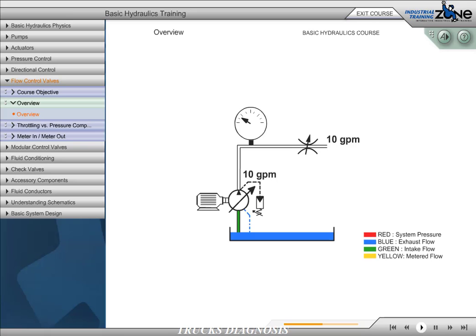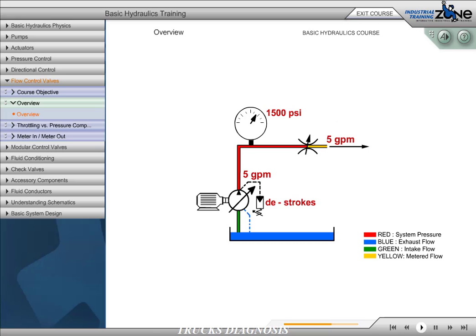When flow control is used in a pressure-compensated pump, fluid is not pushed over the relief valve. As pressure approaches the compensator setting of 1500 PSI, the pump will begin to de-stroke, reducing output flow.